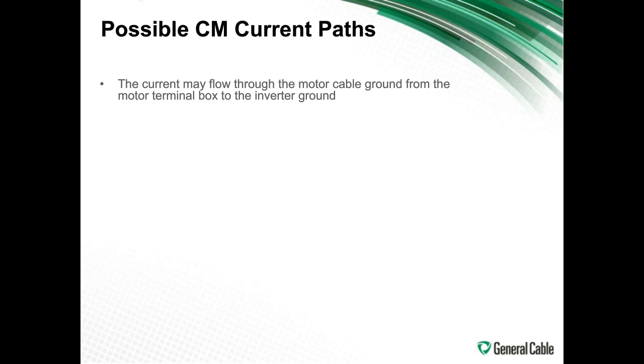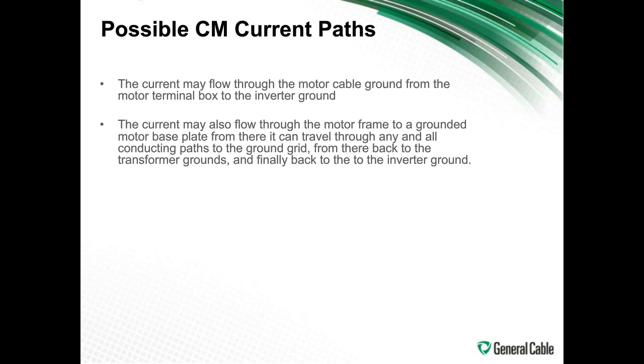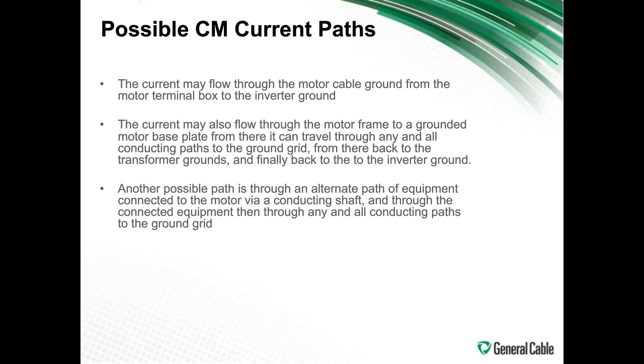So to repeat, the current may flow through the motor ground cable, from the motor terminal box to the inverter ground. The current may go through the motor frame to a grounded motor base plate. It can travel through any and all conducting paths to the ground grid and back to the transformer ground, and finally back to the inverter ground. Another possible path is an alternate path of equipment connected to the motor through the shaft and through the connected equipment, causing trouble along the way.